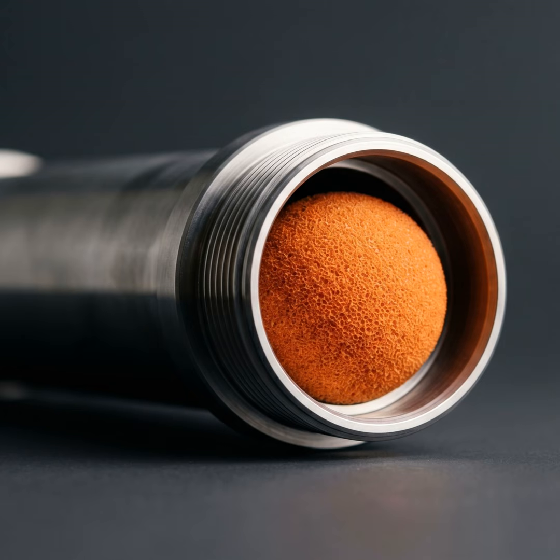Phase change. Exactly. When liquid water changes phase into water vapor, when it evaporates, it absorbs an absolutely monumental amount of thermal energy from its surroundings. Give me some numbers on that. To give you some math on this, it takes just 1 BTU of energy to raise the temperature of a pound of water by 1 degree Fahrenheit. That's sensible heat. Okay, 1 BTU. But it takes roughly 1,000 BTUs to evaporate that same pound of water. Oh, wow, that's a huge difference. Evaporation is a thermodynamic powerhouse.